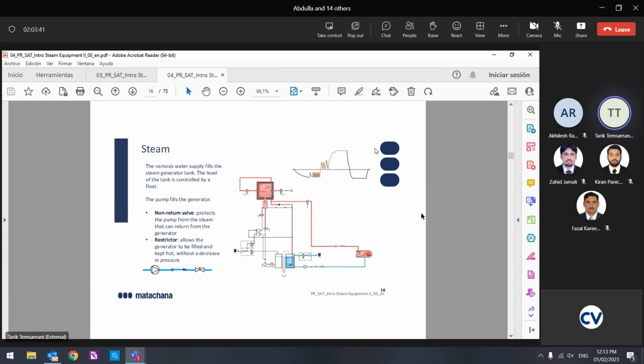So first, we have to check if we have water in the tank. Second point, if there is water in the steam generator. Then whether the heaters are working or not. How many heaters do we have here? Three. Sometimes only one or two work. You don't know because the contactor is the same, and it's on, but the temperature is not rising quickly. That means one of the heaters is not good. Then we have to check this pneumatic valve. It's okay. We have to check the pressure in the jacket. If the pressure in the jacket is okay, that means from this circuit to that, we didn't have any problem. So now we check here.